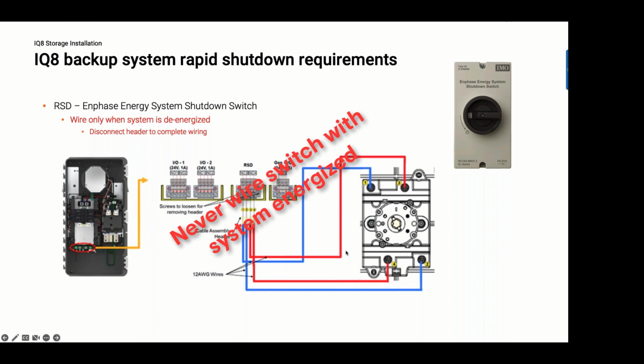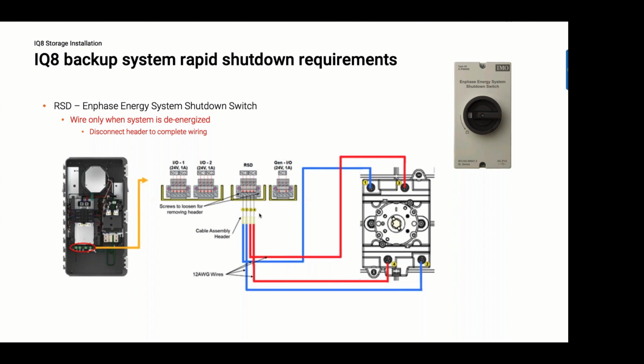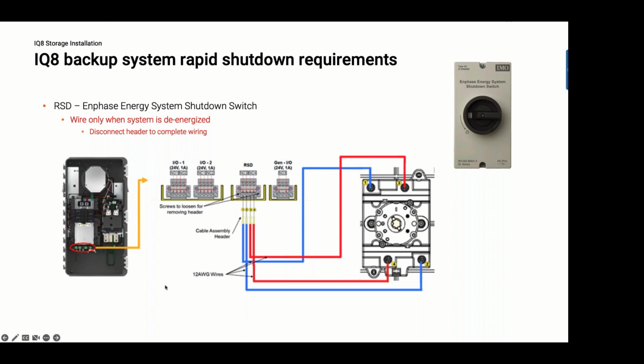Now, we've had circumstances where installers power everything up, they power the house up, and they say, oh, I forgot to put the system shutdown switch in, and you don't want to turn the power off to the house, all right? So you should not wire this hot. So the second way to do this is make sure that you disconnect the header, because there's actually a plug-in header that goes into this port. Remove the header, wire the switch with the header removed, and then plug the header in. If you short something, you could take out a component in the system controller.